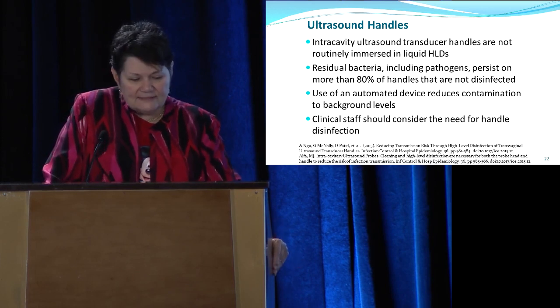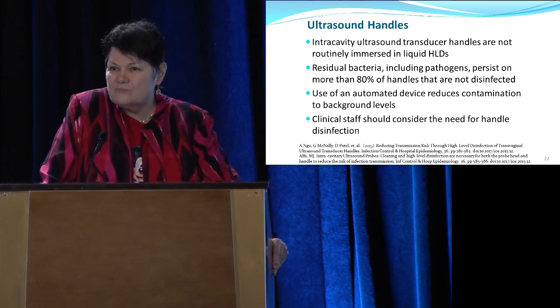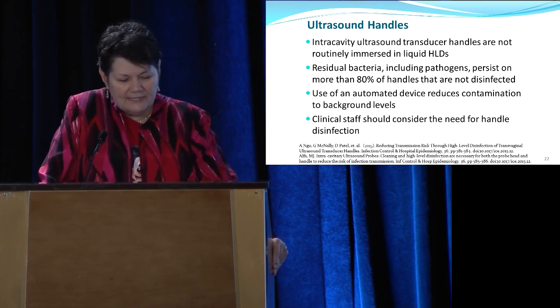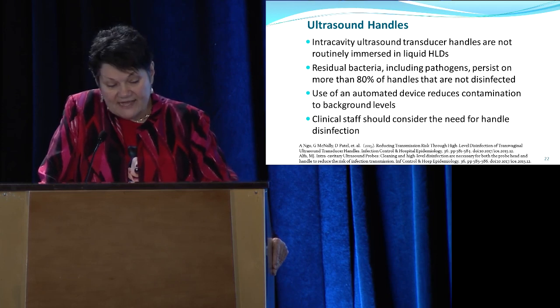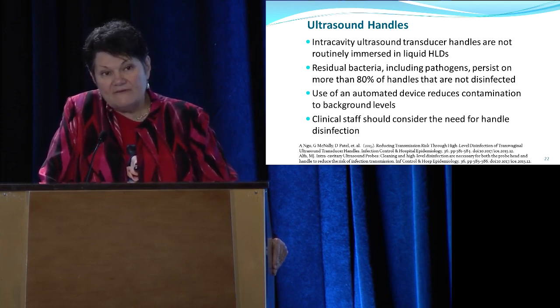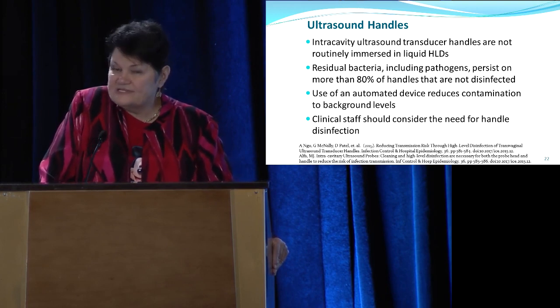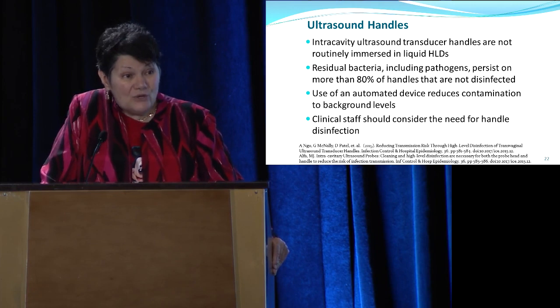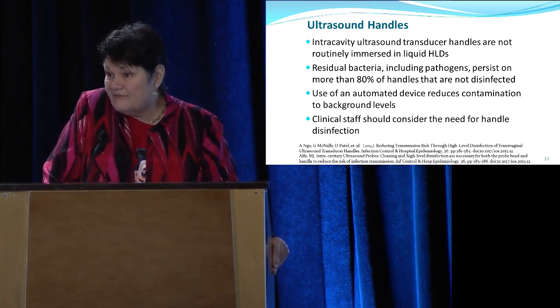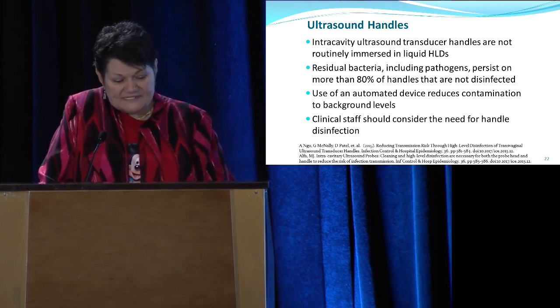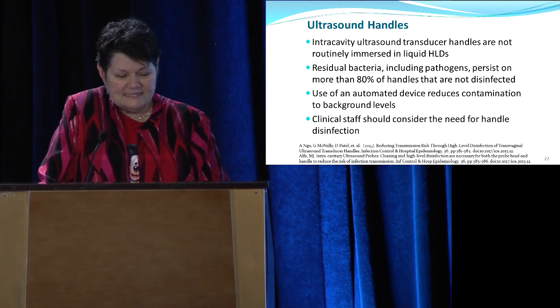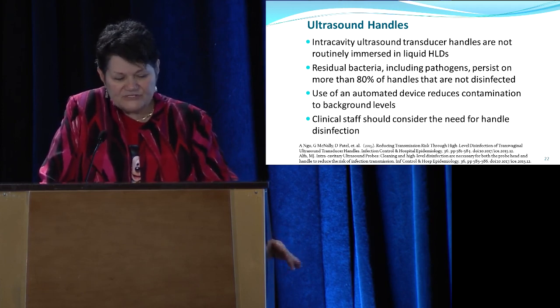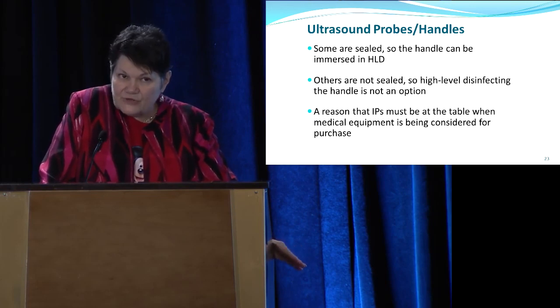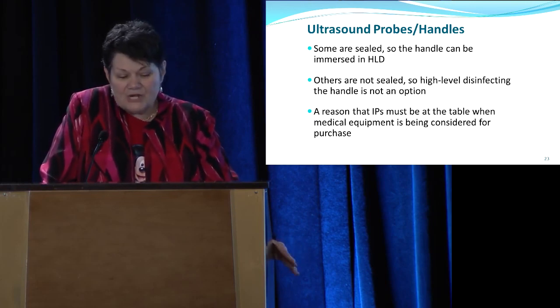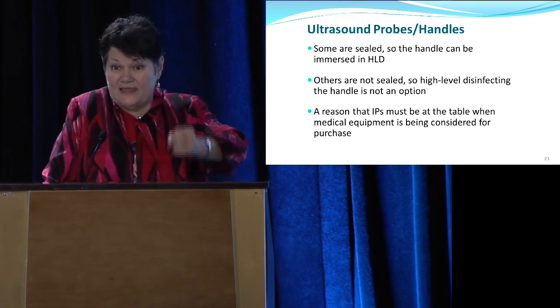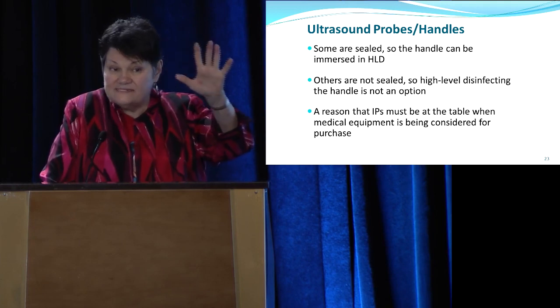So here's a story on the handles: they are not routinely immersed and they grow all kinds of nasty things. They're just awful. The use of an automated device can reduce the contamination to background levels on the handle. And frankly, if I'm coming to your center for a vaginal ultrasound, I want to know that the handle was processed too, because I don't want HPV, thank you very much. I have enough trouble. So the clinical staff needs to have an idea and consider the need for handle disinfection. As I mentioned, some of these are sealed, so they can be soaked. Some of them are not, so high-level disinfecting ends at the business end of the probe and excludes the handle, and that's a bad thing.